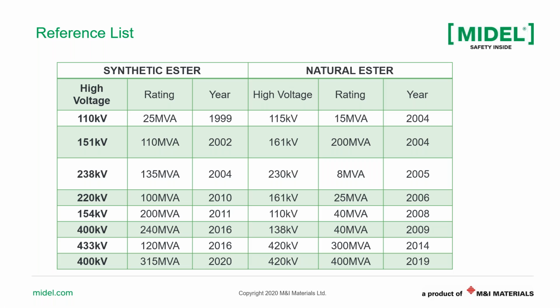And so this is also a short snapshot of our reference list. For power transformers, you can see here synthetic ester and natural ester. As I say, these are just examples with high voltage ranging from 110 kV, 151 kV, and proceeding to 400 kV. Both the synthetic ester and the natural esters are evolving in that range, becoming more and more applied in power transformers. The latest ones are in 2020 and 2019. At the end of the table, you can see 400 kV transformers. One is 315 MVA and the other is 400 MVA, 420 kV.